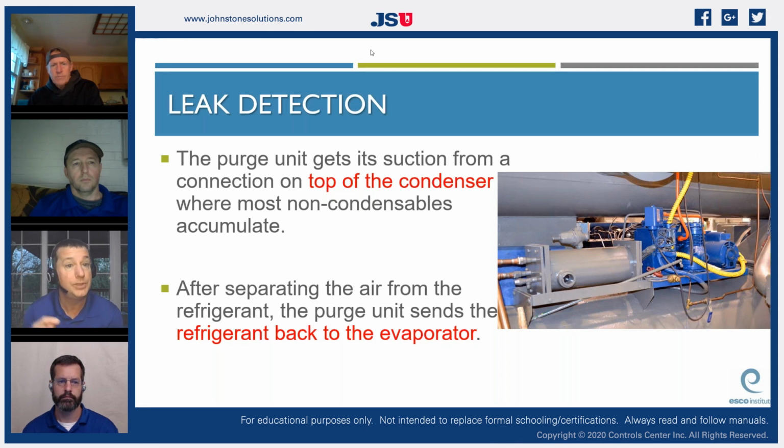And then it's going to try to separate that. That's what it is actually purging. So it's going to try to separate that air and moisture from the refrigerant, and it's going to try to put the refrigerant back into the system. The downfall of that is even the most advanced systems cannot completely isolate all of the refrigerant from the air and the moisture.